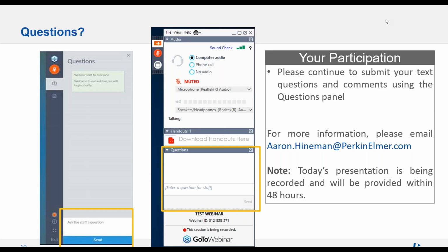And sometimes when you have a whole bunch of unknowns, and you know that some of your unknowns could be really high in that particular element, sometimes I'll run in both. So it actually effectively extends your working range, right? Exactly. Great point. And sometimes I'll name them differently, like sodium low, sodium high, or whatever. Exactly.